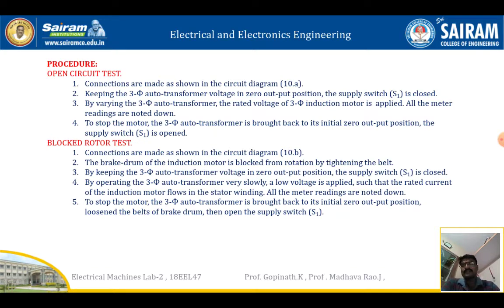For the blocked rotor test, connections are made as shown in the figure. The brake drum of the induction motor is blocked from rotation by tightening the belt. With the 3-phase auto transformer at the zero output position, the supply switch is closed. By operating the auto transformer very slowly, a low voltage is applied such that the rated current of the induction motor flows in the stator winding. All the meter readings are noted down. To stop the motor, the auto transformer is brought back to the initial position. Loosen the belts of the brake drum, then open the supply S1.